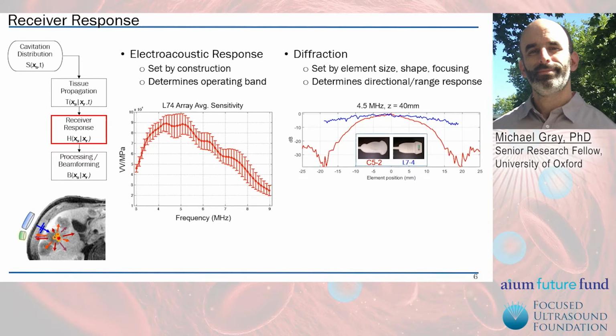The other important effect to keep track of here is diffraction, or if you like, near-field directivity. And this is set by element size, shape, and focusing. To illustrate this, I've got measurements here for two different commercially available arrays, both looking at 4.5 megahertz and a source that's 40 millimeters away off the central axis of the array. Now, the general trend for diffraction is that it lowers the responses at the edges of the array, and clearly the array type has a lot to do with that. So starting with the L74, the linear array, we have about a 6 to 9 dB effect here at 4.5 megahertz. And this may not seem like that much on this scale, but it will in fact change the effective aperture of the array and also impact the energy estimates if you don't tell the beamformer that this is happening.